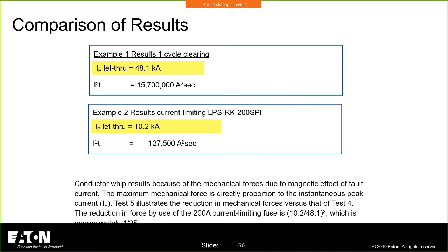So before I go on, I'm just going to look at comments. Can you explain real quick the fuses? I missed the point earlier. Okay, I already talked to that one. Are fuses now rated 1,000 volts to match the NEC? No, not necessarily. They don't necessarily have to be all moved to 1,000 volts. They moved the code to 1,000 volts, but I don't necessarily need a 1,000 volt fuse.